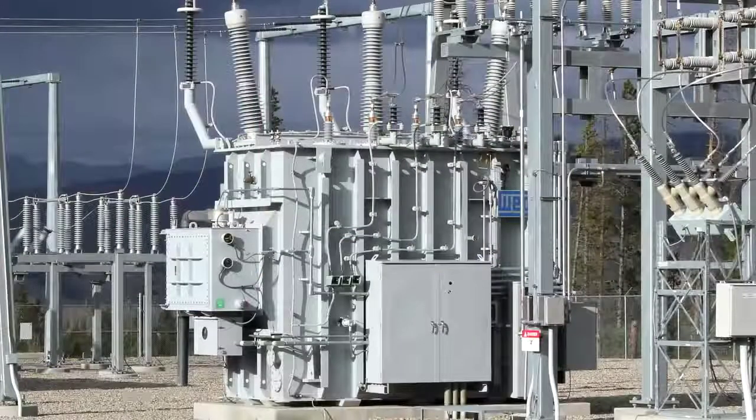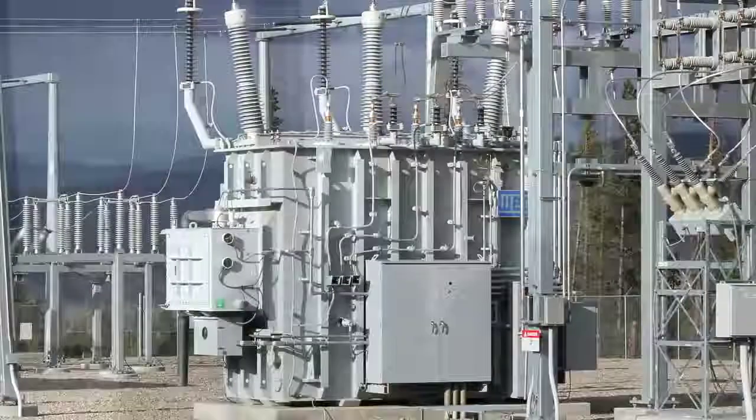So the complexity of coupling it's called a high phase order line, of coupling that into a substation sort of defeats the economics of it. Although periodically people raise the question because it would be possible, for example, it's very easy to couple from 12 phases through a transformer down to 3 phases. But it remains an intriguing concept, probably more useful for power educators than for transmission line companies.